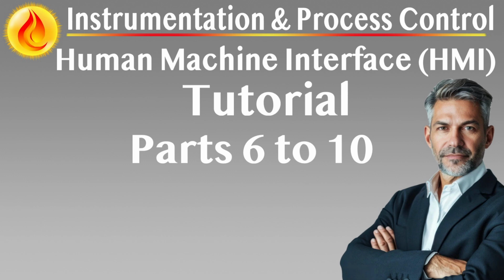Alarm behavior by plant condition. Different plant operating states require different alarm handling techniques. Steady state, alarm grouping, suppression of inactive systems. Upset conditions, active suppression of expected secondary alarms, prevent overload. Startup, shutdown, dynamic alarm settings and masking of irrelevant alerts. Plant stopped, static suppression of alarms from equipment known to be offline. These behaviors must be embedded in DCS sequences or logic blocks, governed by operating modes and permissives.